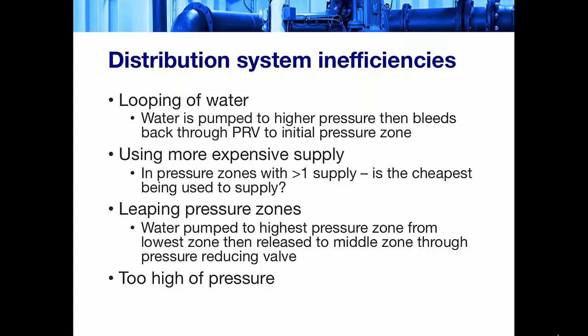Another inefficiency within distribution systems is using a more expensive supply. This can happen both in groundwater and surface water supplied water systems. So basically, are you using the cheapest supply possible when you're supplying a pressure zone? This is more common with larger systems or rural water districts that have a lot of variable terrain within them. But one of the main costs for water supplies is the energy cost. So if you're running, say, for example, water from a well that has a water table 500 feet below the surface and are not running water from the well that's 100 feet below the surface of the ground, that would be a good example of you're using the more expensive supply.